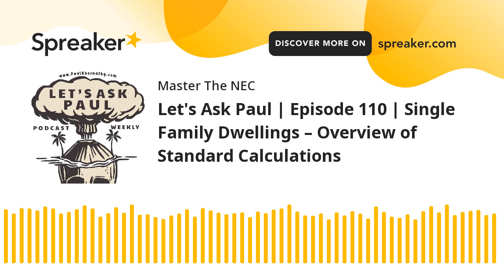Where do I get that? Well, that's in 220.61(B). And 220.61(B) tells me that I can take an additional demand, right? And that additional demand is that 70%, right? So I take whatever the VA is based on my ungrounded hot conductor calculation, and I simply multiply that by 70%, and that's the part that I take for my neutral contribution. And that's the same thing for the cooking appliance.